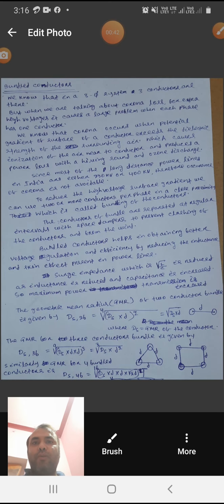Now what is corona loss? Corona loss means when the surface potential gradient of a conductor exceeds the dielectric strength of the surrounding air, then corona loss occurs. This causes ionization of the air surrounding the conductor and produces a power loss with a hissing sound and ozone discharge. Okay, this is called corona loss. That means if each phase has one conductor for extra high voltages, then obviously corona loss will cause a large problem there.